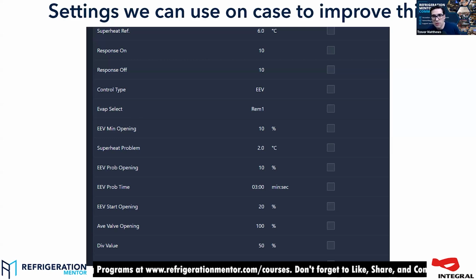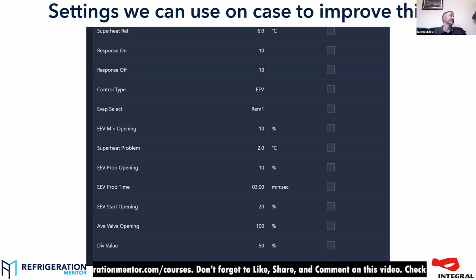If you drop that too low, we need pressure differential, and this is the same with the EEVs. Go ahead. One thing to consider: some rack manufacturers who do an LT only system, if you've got no medium temperature loads, they will just let the flash tank open to the high stage compressors. There'll be no valve in there, so that liquid pressure will be a lot lower. It might be 30 bar, 450 psi, whatever. It'll be down at the MT suction condition, which does mean you can run the gas cooler lower because you'll always still have the push out of it. But it's a different type of system. So as you say, one size doesn't fit all. LT onlys do give you a bit more operating range like that if they float that pressure.